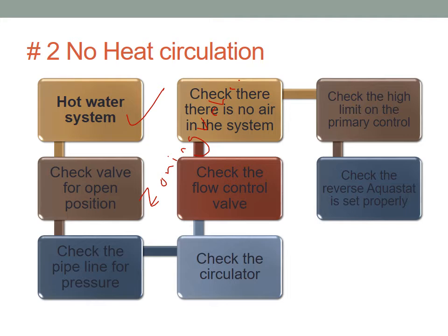Check the circulator, make sure it's giving off enough pressure. Make sure also it's on. Check the flow control valve, that it's installed correctly, it's not faulty in the closed position. Check that there's no air in the system.